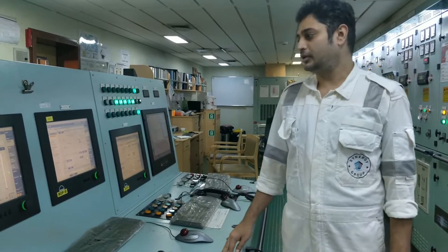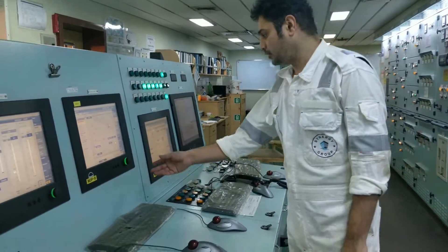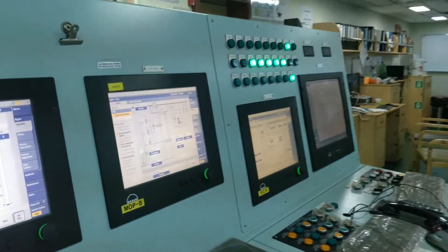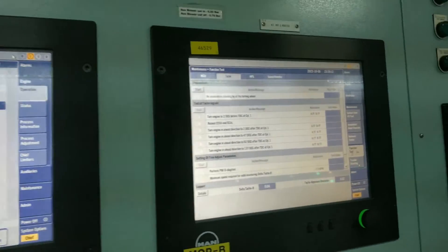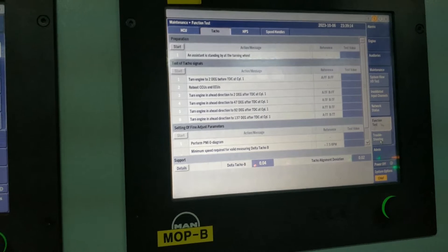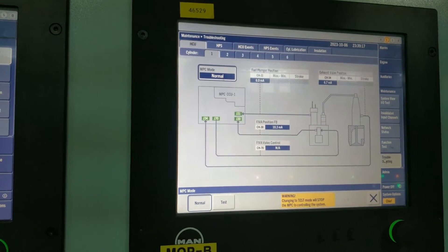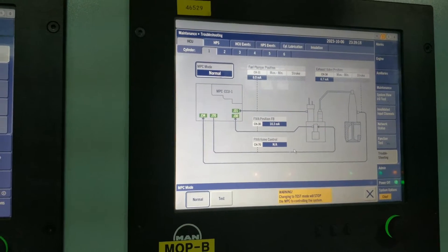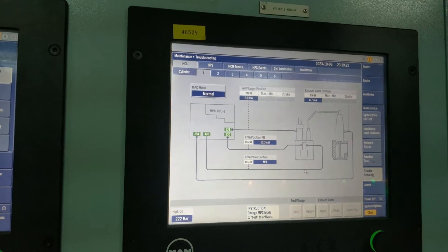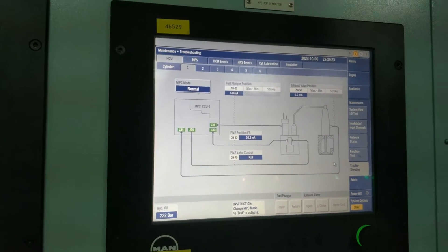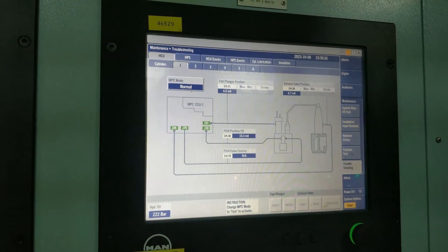For doing the HPS test, you can go to Maintenance, then Troubleshooting. Suppose I want to do the cyclic test for the exhaust valve and fuel valve — just to open and close.